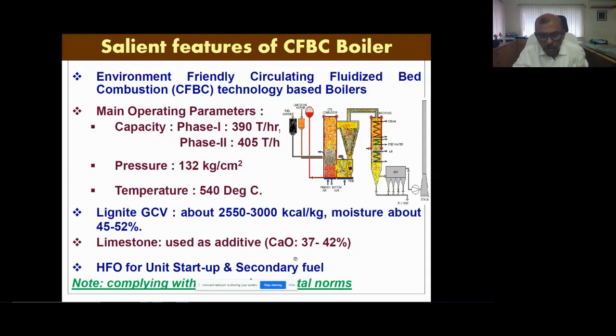Otherwise, on the SOx and NOx parts, we are fully complying. Instead of the limit of 600 for SOx, we are complying in the range of 50 to 150 mg per Nm³. NOx also has a limit of 600, and we are much below, only around 40. SPM is 50 to 110 in phase 1 and 30 to 60 in phase 2, where its limiting value is 50.